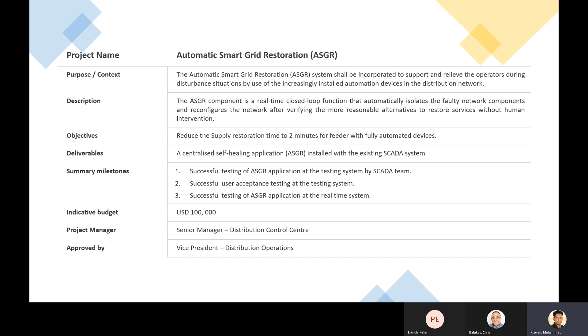Okay. And what sort of time frame are they looking at for implementing this? Yeah, it's a 1-year project starting from today. Oh, okay. I will just tell you some of the operational rules for this application in the 33 or 66 kV network. So there are 3 simple rules. Number 1, the area of operation for ASGR based self-healing shall be restricted to 33 kV radial circuits only. We will not utilize this application on the ring configurations. This will be used only on the radial configuration of the circuit.